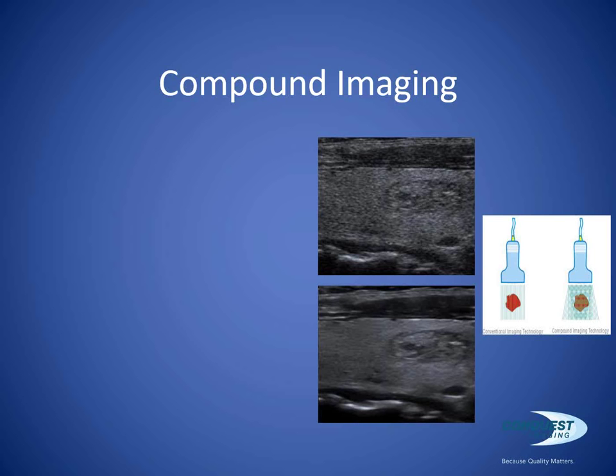I was actually demonstrating this at the site I'm at earlier. If you have an ultrasound system and you have the probe activated, you can turn compound imaging off and put, say, a paper clip on the face of the probe, and you'll create a really bright line going down the middle of the image. Then if you turn on compound imaging, you'll actually see the system firing at all the different angles. It's actually kind of cool to look at. So the next time you're in front of a machine, I encourage you to do that. It's a really cool technology.